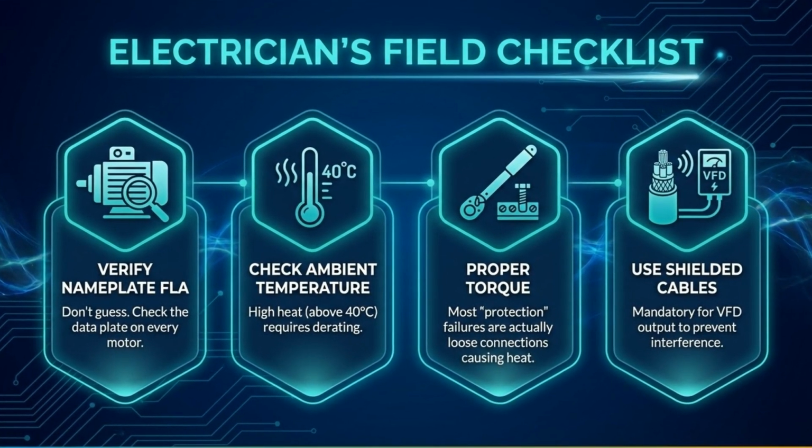As part of your field checklist, always verify the nameplate FLA, check ambient temperature for derating needs, ensure proper torque on connections, and use shielded cables for VFD output to prevent interference.